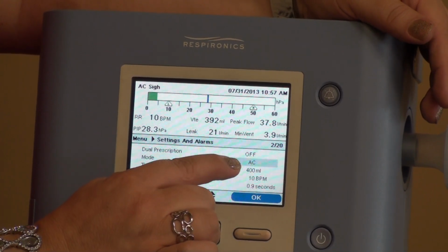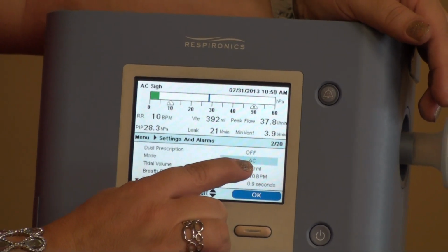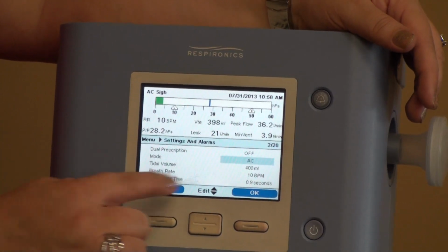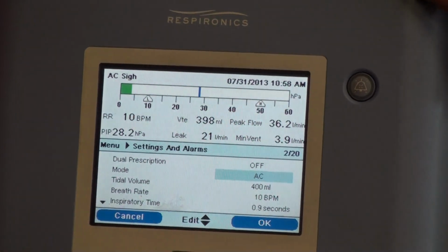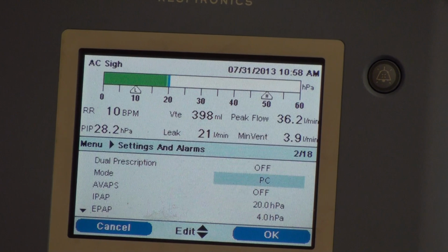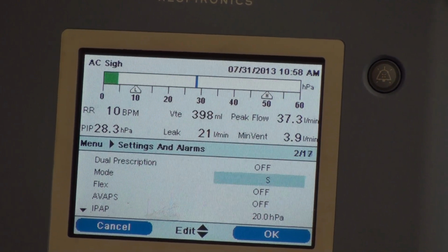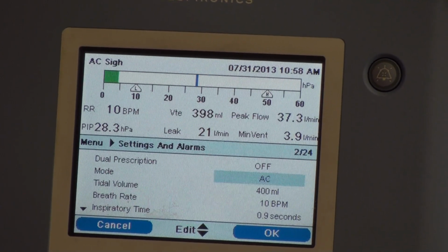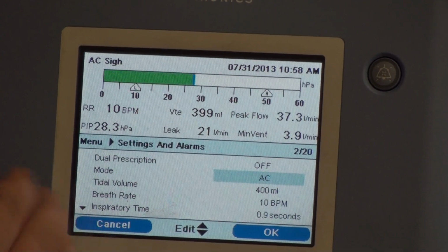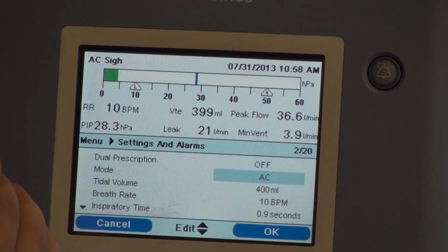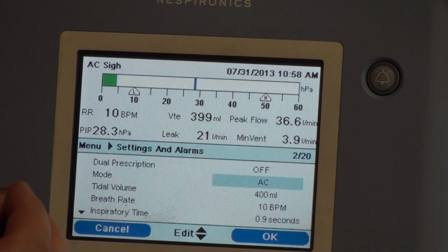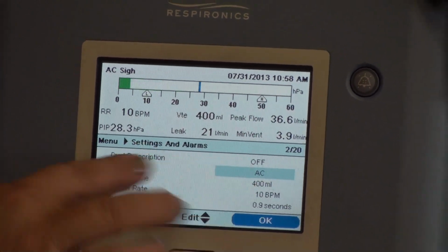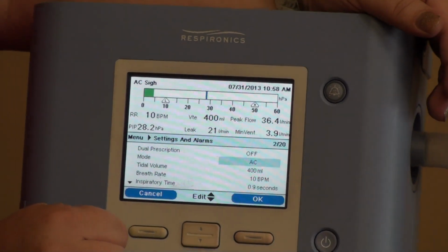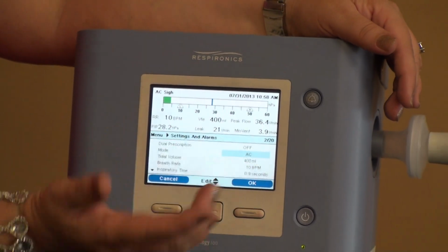Right now it's on assist control. As I toggle through the different modes, notice how these parameters change according to what mode I'm in. Every time I go down here, it changes to whatever parameters are for that particular mode, which is a really nice feature because you might get an order and think, well, do I set this or don't I set this? Well, if it's on here, then you need it to be set.